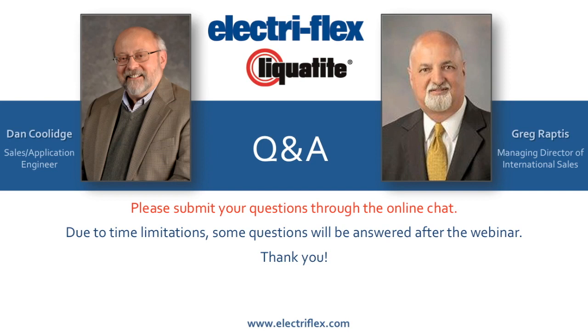Do the shielding conduits require special prep to accept the fittings allowing for proper grounding? Another great question. No, our Shield-Flex series requires no prep other than a good, clean, square cut. There is no need to remove any of the jacket like you might for shielded cables. As Greg just mentioned, a standard liquid-tight metal connector is used, and they contain a grounding ferrule which screws directly into the interior of the conduit, making secure contact to the inner core.